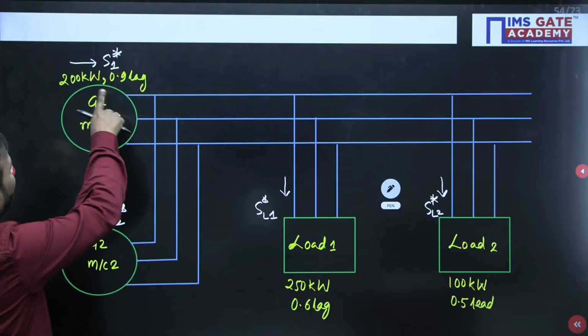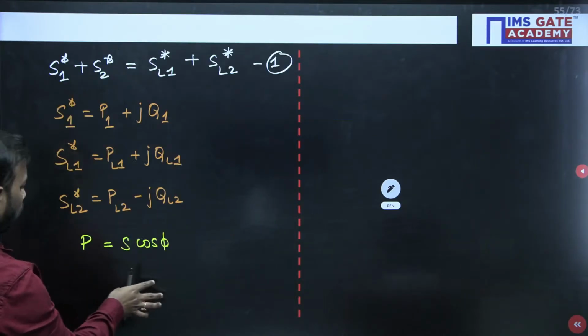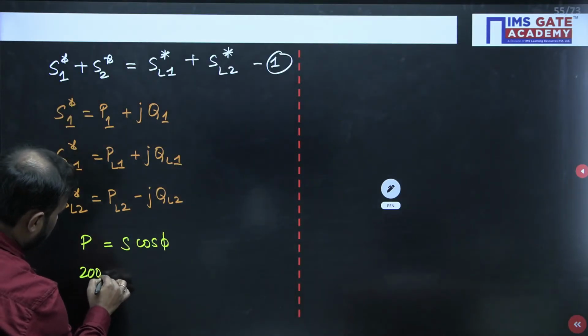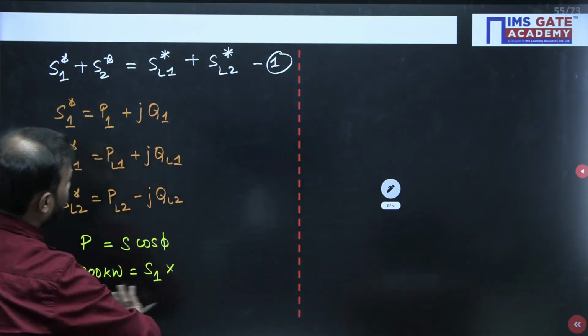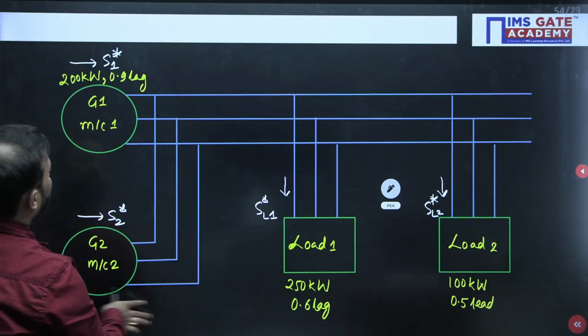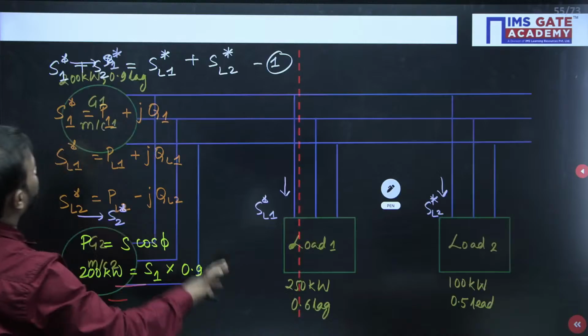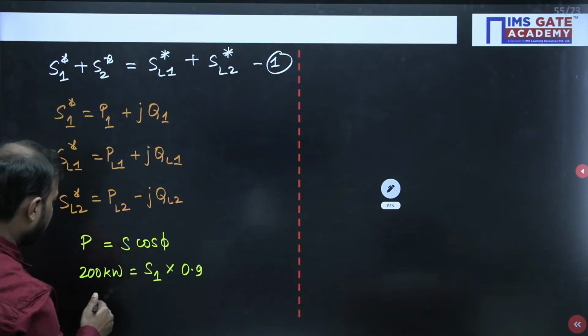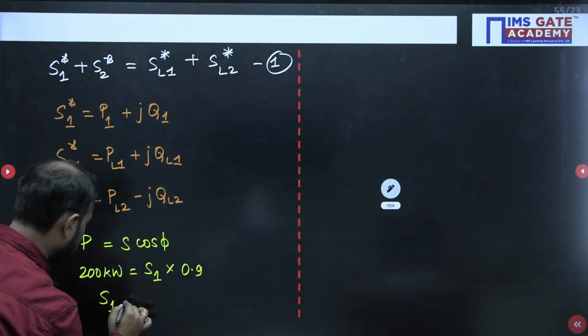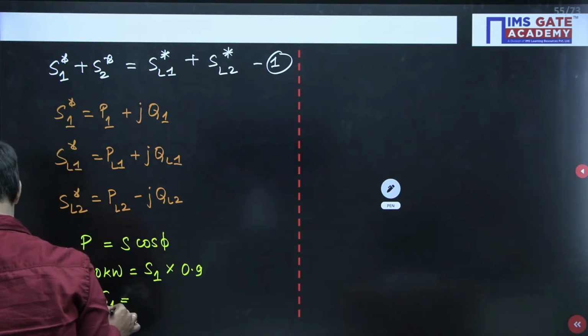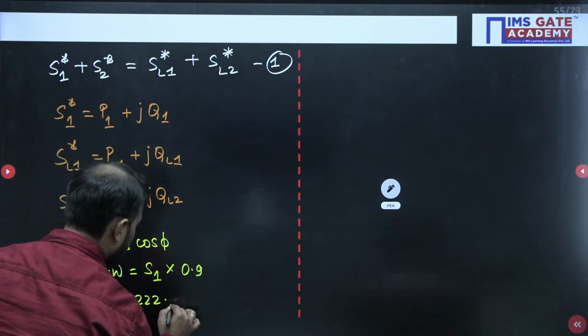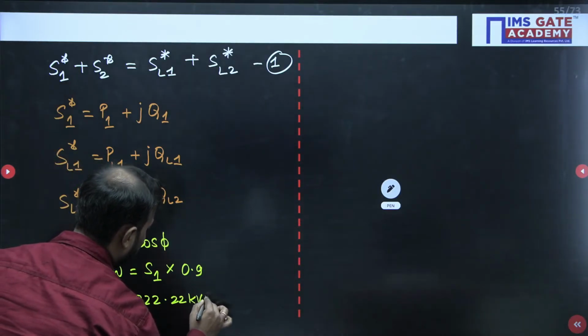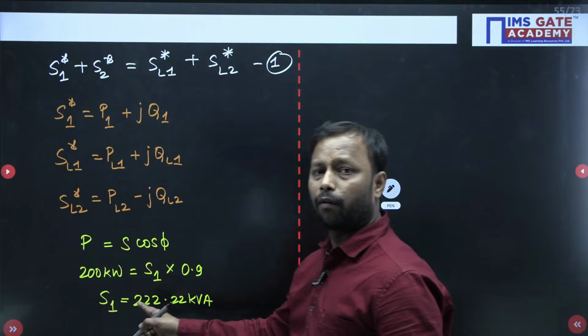For generator 1, real power is given as 200 kilowatt, and it equals S1 into cos phi, where cos phi is 0.9. So S1 comes out to be 222.22 kVA. This is the apparent power.